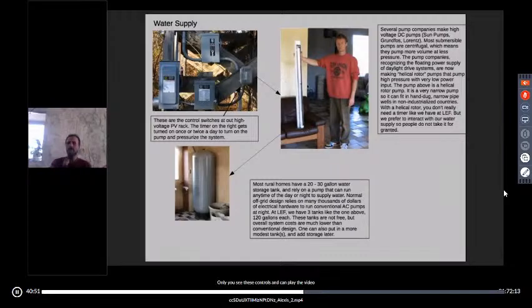But I personally believe the centrifugal pump will probably have a longer lifespan. You could put that centrifugal or helical rotor pump on a pressure switch and run it just like an AC pump, but in cloudy weather it would run a lot because it takes a long time to bring up pressure. We run it on a timer instead, so the pump doesn't run as hard. I think we'll get 20 years out of our pump that way. We're trading off a little bit of manual control for extending our pump life, at least I think that's what we're doing.